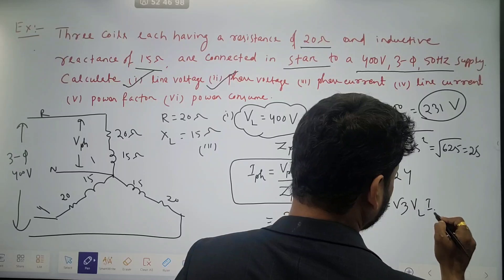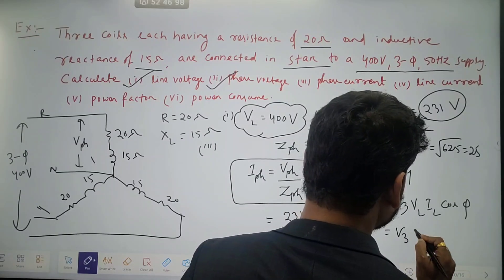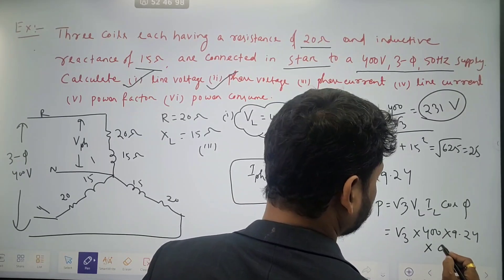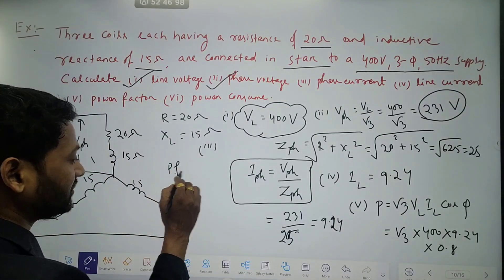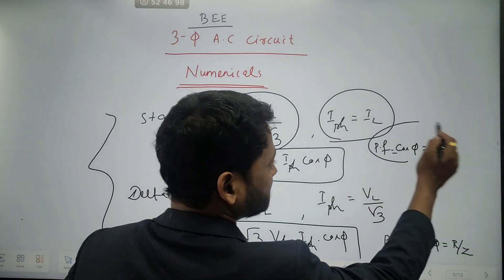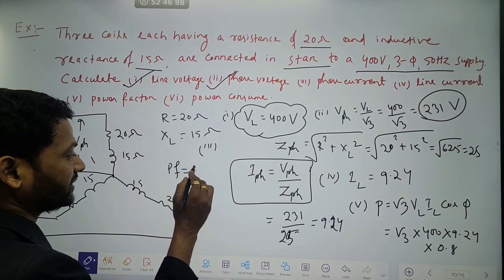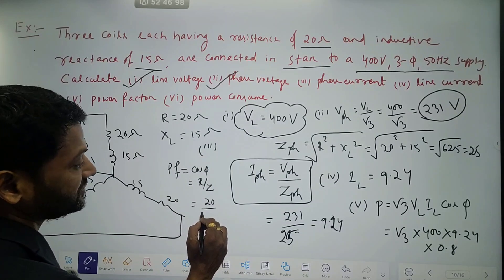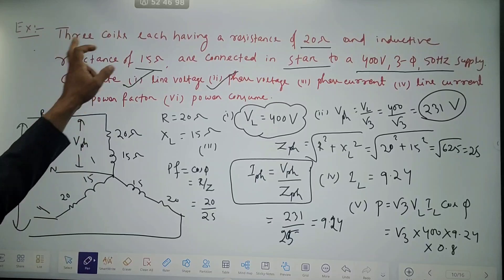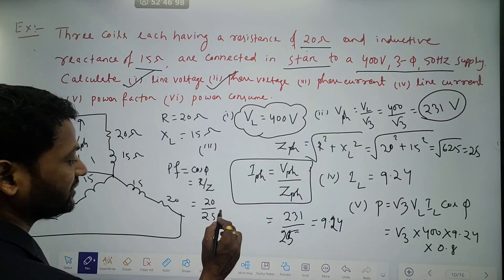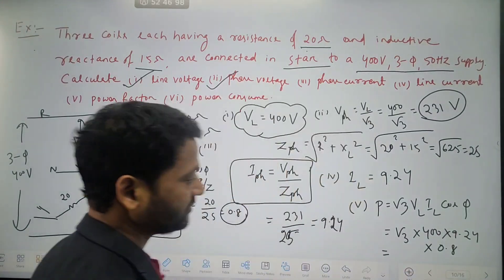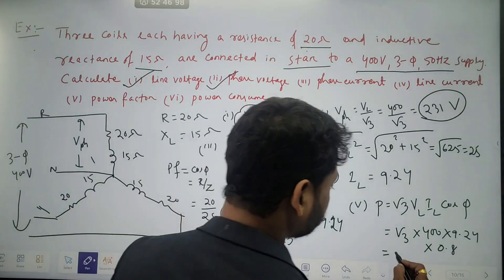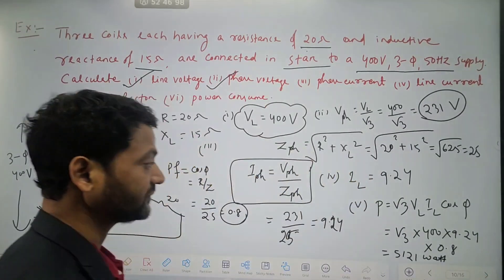Power is root 3 times VL times IL times cos phi. Root 3 times VL is 400, IL is 9.24, and power factor — cos phi is R by Z, which is 20 by 25, coming to 0.8. So power is root 3 into 400 into 9.24 into 0.8. If you multiply, the answer is coming 5,121 watts.